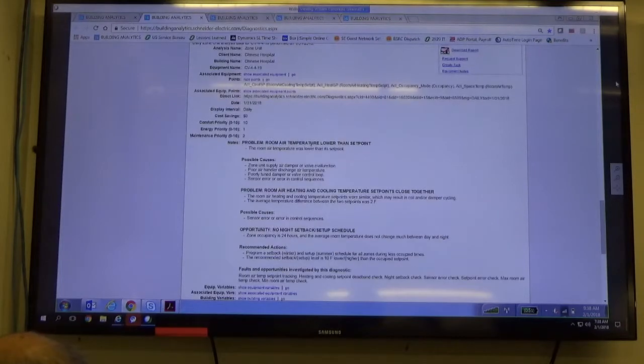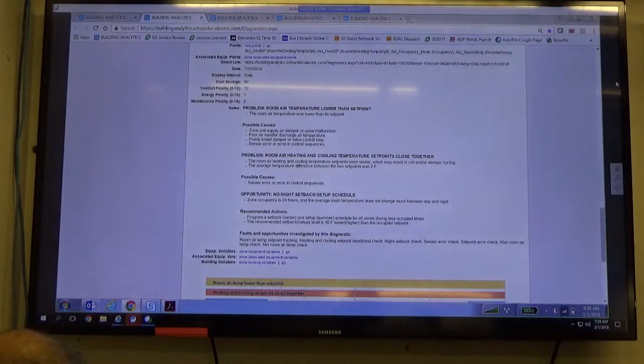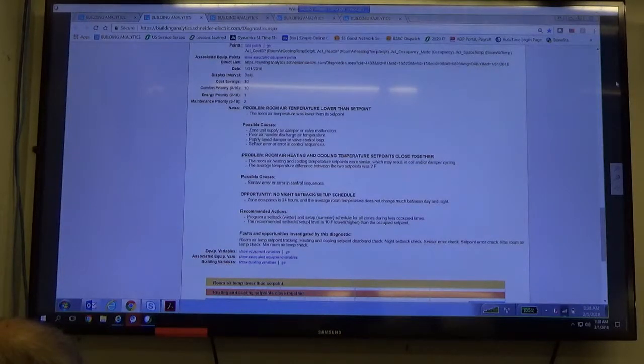And it'll show you the diagnostic is room air temp lower than set point. It'll give you causes for this, like zone unit supply damper, valve malfunction, poor AHU discharge air temp, poorly tuned damper, valve control, or sensor error.